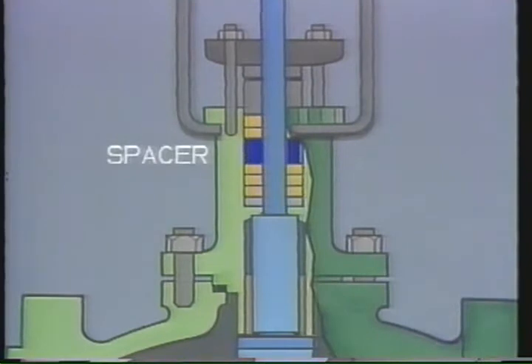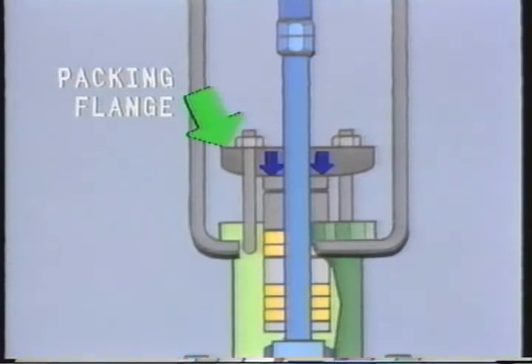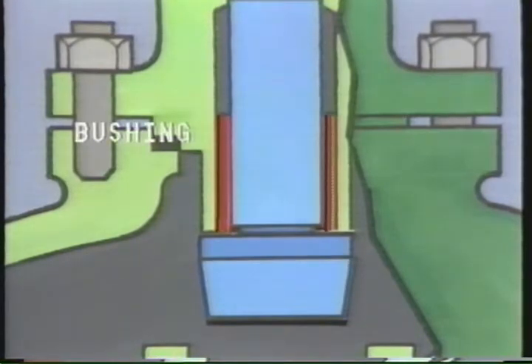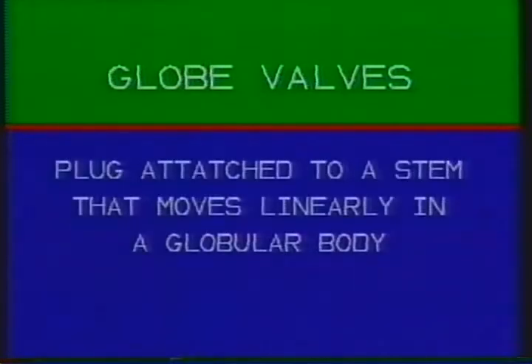A spacer is included in the stuffing box when the needs of the system don't require a stuffing box to be completely filled with packing. The packing flange puts pressure on the packing follower, which compresses the packing material inside the stuffing box. Beneath the packing assembly, the bushing helps guide the stem. We've seen an example of a common type of valve, the globe valve. Some other designs of globe valves are described in your text. The feature they have in common is a plug attached to a stem that moves linearly in a globular body.